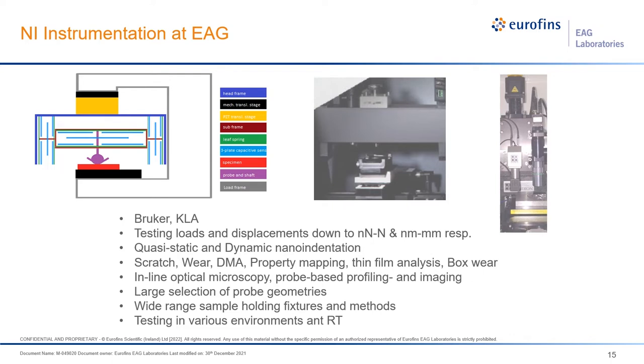One instrument also has a piezo translation stage, which allows imaging with the same probe in contact mode. We have testing capabilities with loads ranging from nanonewtons to newtons, and displacement ranging from nanometers to millimeters. We can perform quasi-static indentation, dynamic indentation, scratch testing, property mapping, thin film analysis, and wear studies. An experiment typically starts by looking optically at the sample, as the optical microscope is in-line with the indentation head. After an automatic move to the indentation head, we can also do higher resolution imaging using the tip itself — either 1D profiling or 2D area imaging — to select an area of interest or study indentation-induced artifacts.